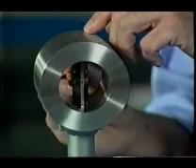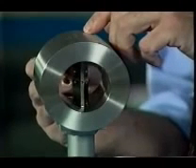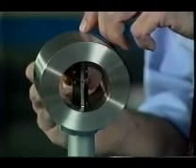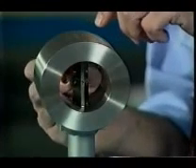There are several acoustic techniques we can use to measure flow velocity. One technique, called the time of flight technique, uses the difference in the speed of the wave as it goes downstream in a flow system compared with going upstream. Because the acoustic wave will go faster as it gets carried along with the flow, we can then infer flow velocity by comparing a wave sent upstream with a wave sent downstream.